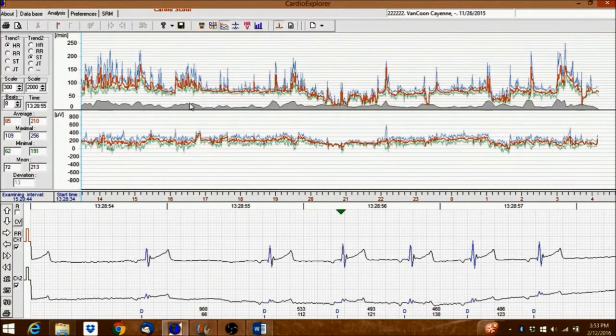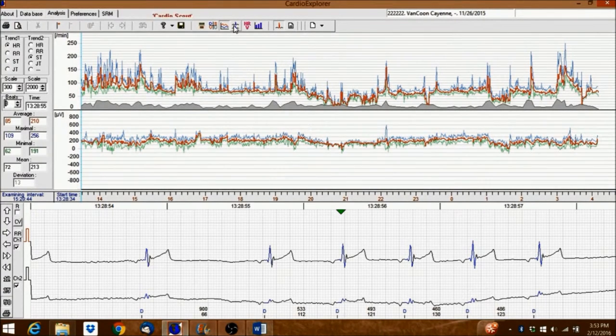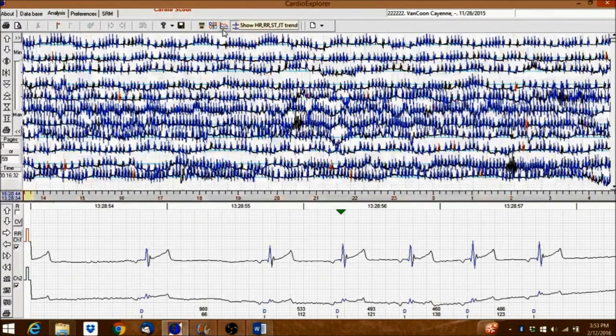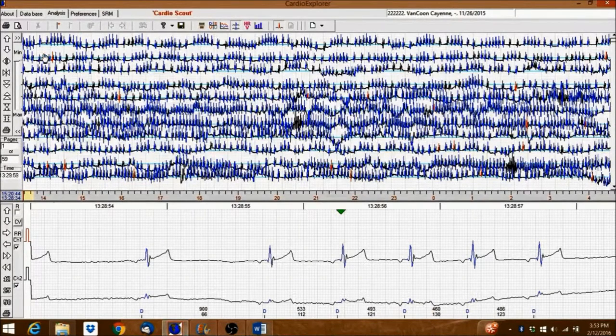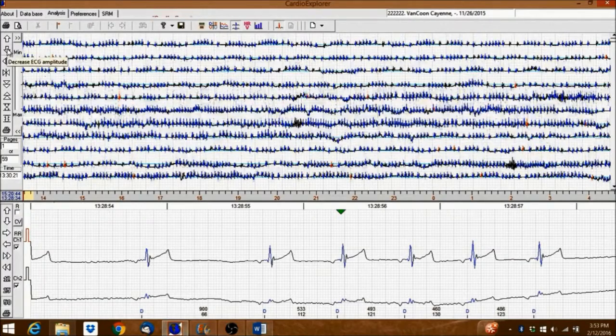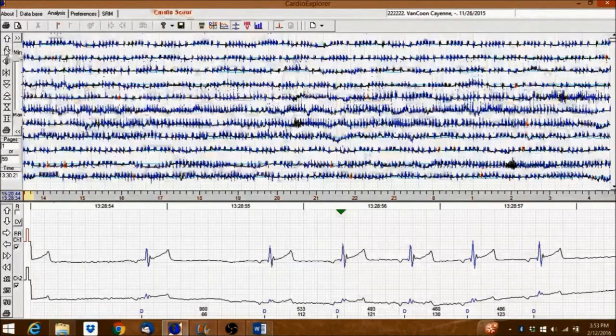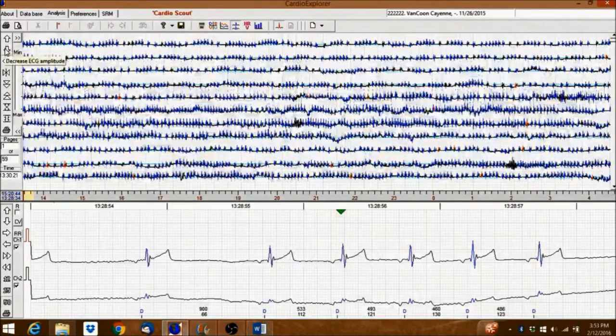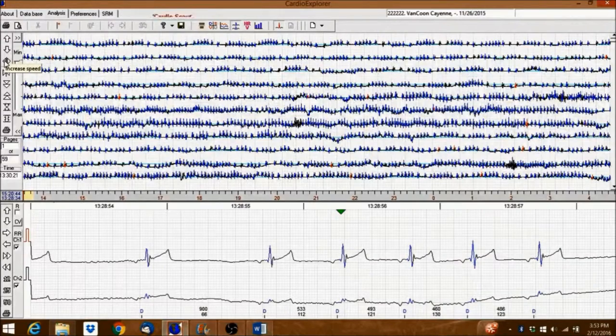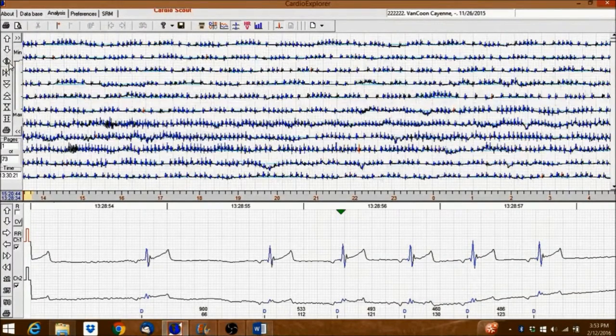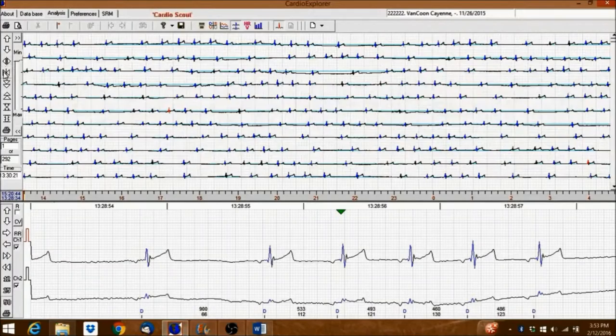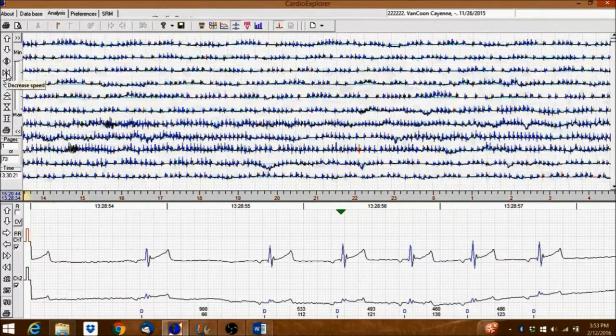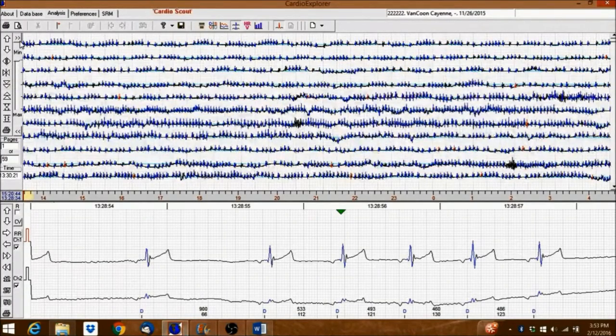Click on the Full Disclosure icon to show the entire recording at a glance. The up and down arrows adjust the amplitude. The left and right arrows increase and decrease the paper speed. And the up and down arrows scroll through the pages of the recording.